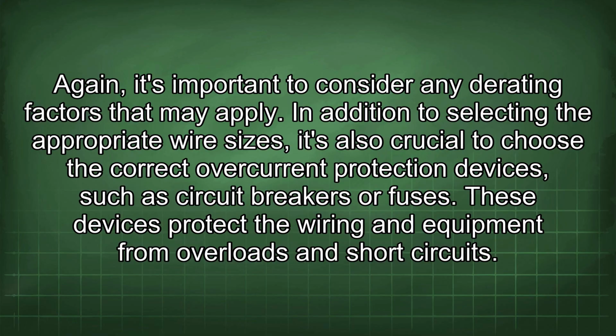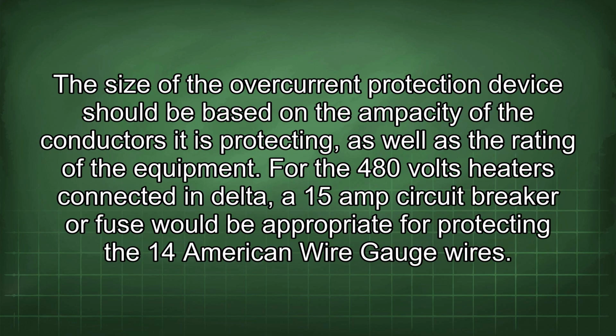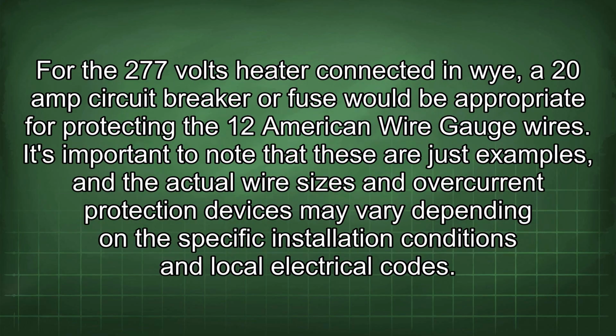In addition to selecting the appropriate wire sizes, it's also crucial to choose the correct overcurrent protection devices, such as circuit breakers or fuses. These devices protect the wiring and equipment from overloads and short circuits. The size of the overcurrent protection device should be based on the ampacity of the conductors it is protecting, as well as the rating of the equipment. For the 480 volt heaters connected in Delta, a 15 amp circuit breaker or fuse would be appropriate for protecting the 14 American wire gauge wires. For the 277 volt heater connected in Y, a 20 amp circuit breaker or fuse would be appropriate for protecting the 12 American wire gauge wires.